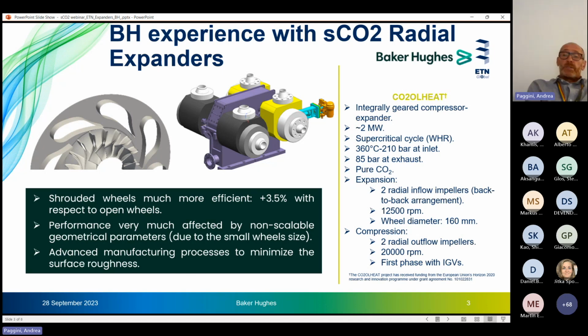And so as far as concerned clearances, even if a shrouded design for the impeller, for the wheel, is more critical and challenging from the standpoint of the mechanical design, it allows to have a better control of the clearances resulting in 3.5% of efficiency gain with respect to the open wheel.